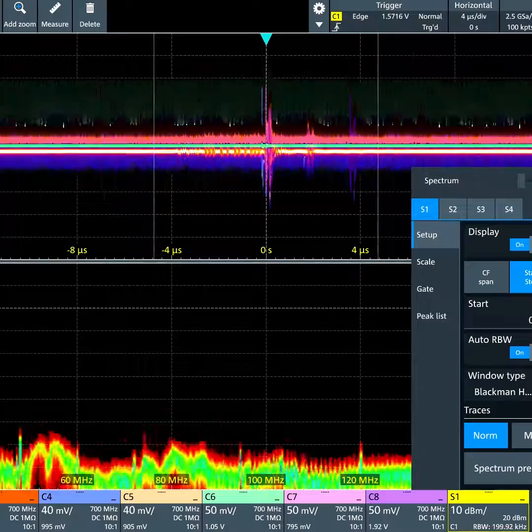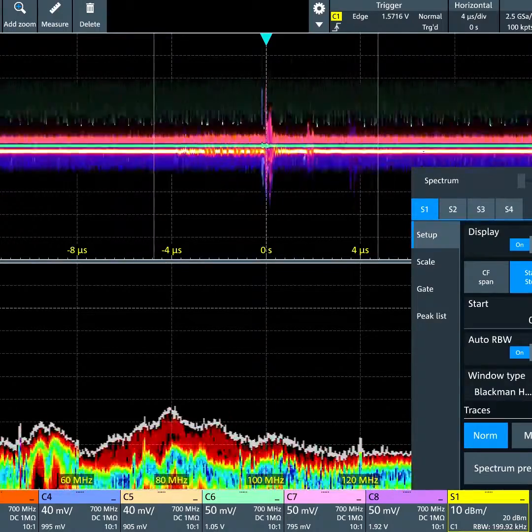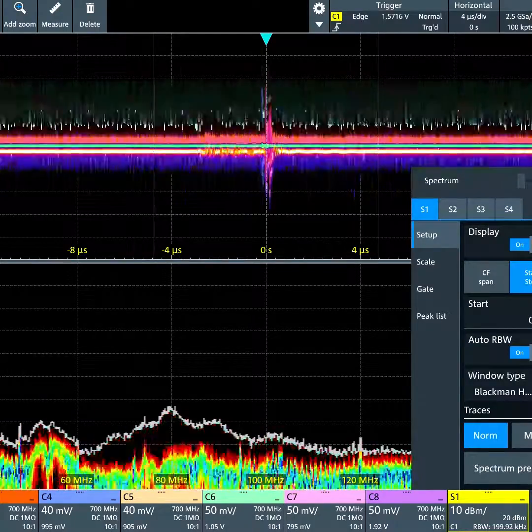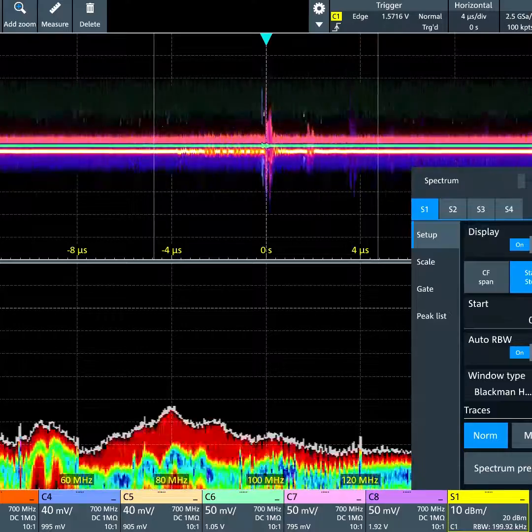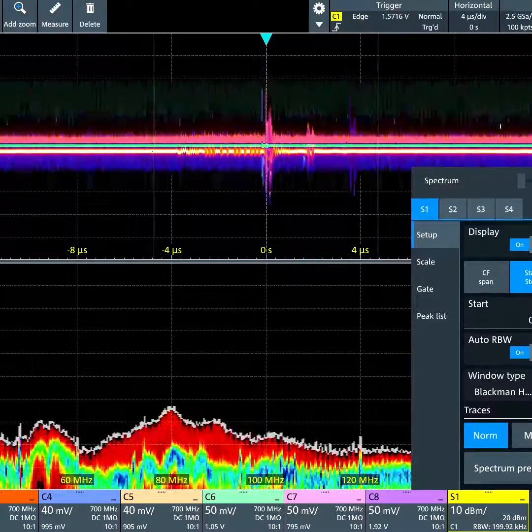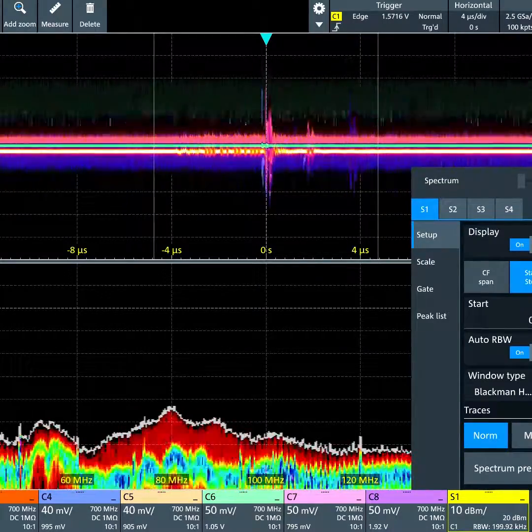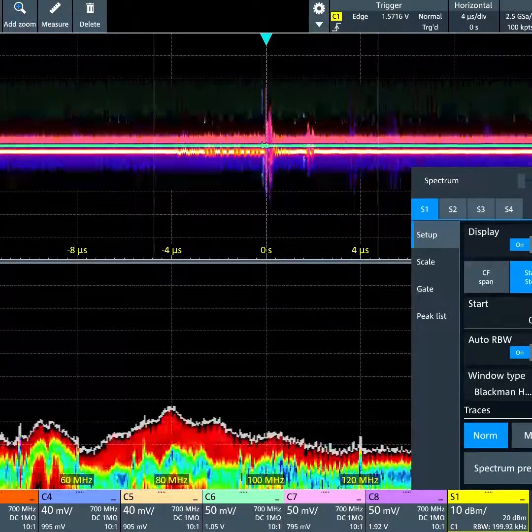For example, I might want to use a max hold detector. You can see now I turn that on and there's a white trace above the color spectrum display, which is holding the peaks. This is often useful for EMI testing.